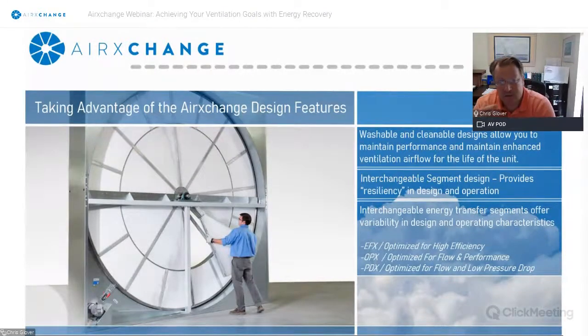I've kind of been speaking in terms of flexibility. There's been a lot of discussion in regards to building resiliency, which to me means being able to operate effectively in future periods of crisis in terms of HVAC system design and operation. In my interpretation, resiliency in regards to energy recovery ventilation is being able to maximize airflow delivery to the space without losing control of occupant comfort. This could mean sizing the HVAC unit for periods of operation where the outside air would be above the minimum requirements for a certain amount of time, or maybe replacing existing components with new components that may achieve that goal a little bit easier.